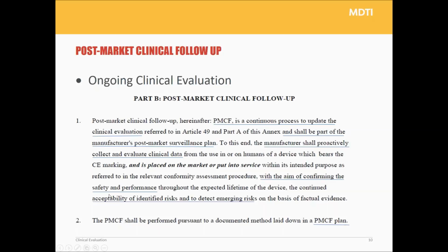The aim of it is to confirm the safety and performance and the acceptability of identified risks, and importantly to detect emerging risks. And you need to have a post-market clinical follow-up plan, which as previously stated is part of your post-market surveillance procedure.